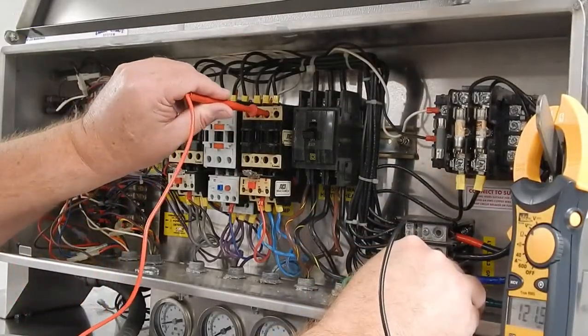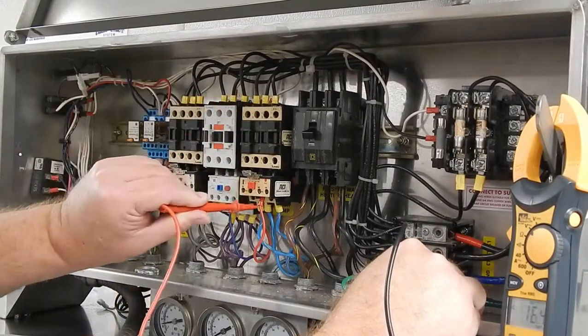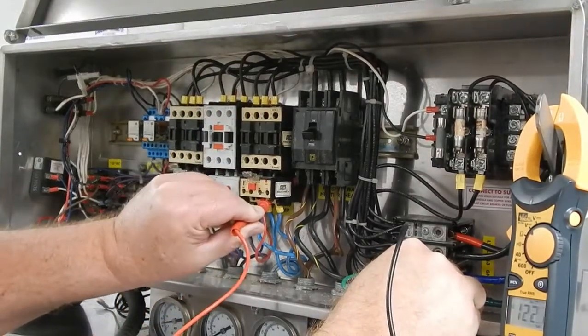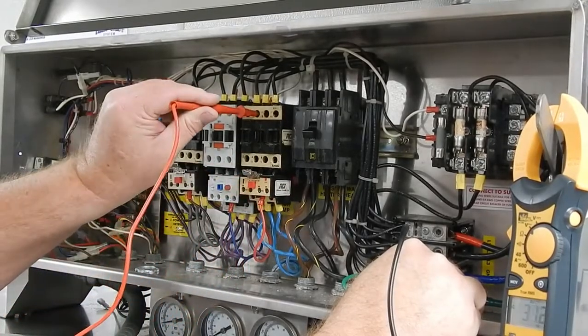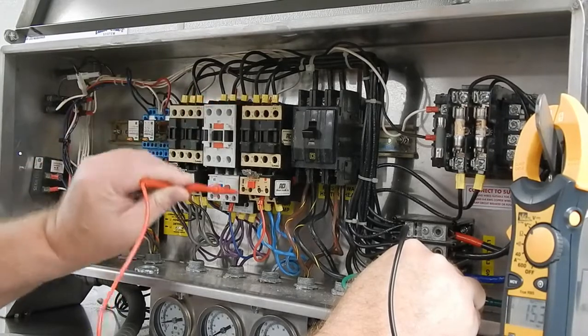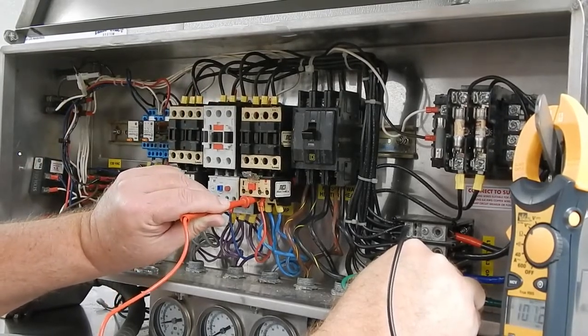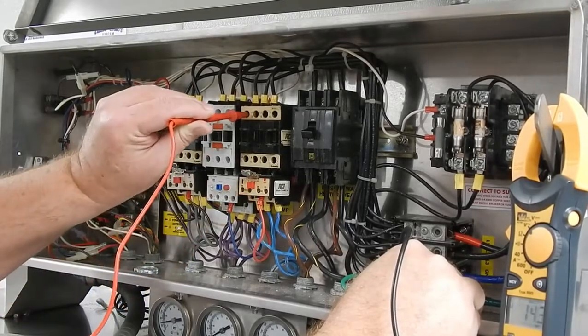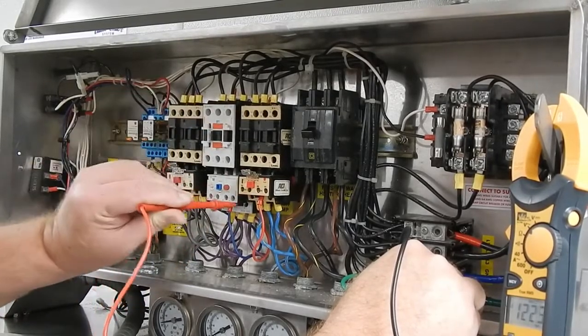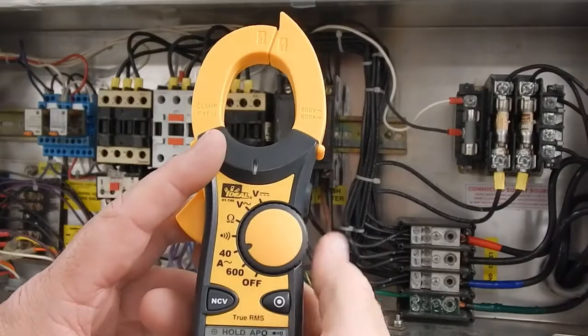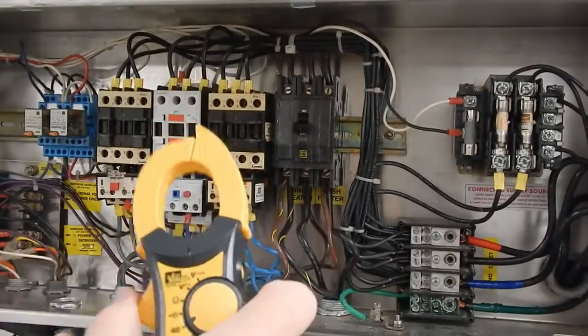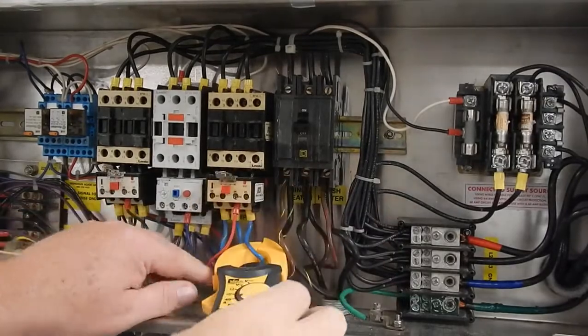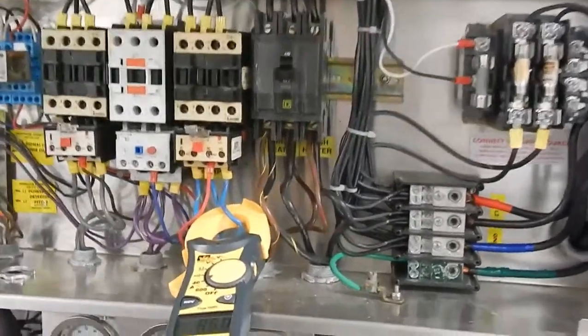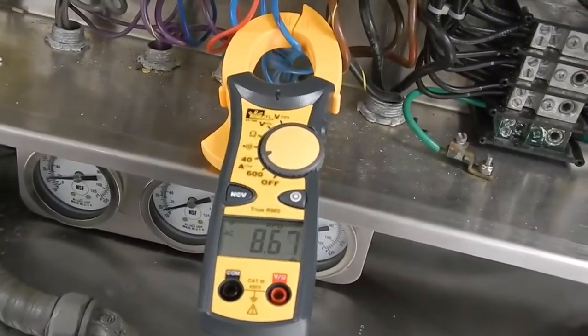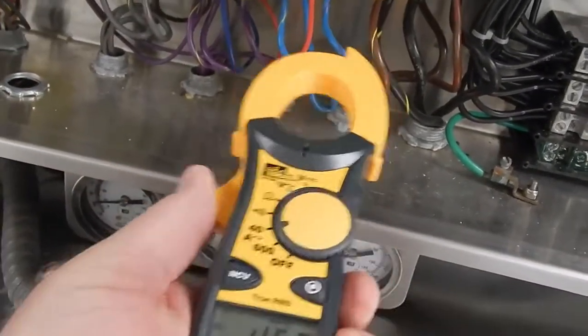Next, we're going to check our voltage coming into the contactor and what's coming out. We want to verify that there is correct voltage on each leg coming through the contactor. Remember, a drop in a leg or low voltage can cause the motor to draw more amperage, causing more current to flow that can trip an overload. Next, we're going to take our multimeter, set it to amp settings, and we're going to test one leg at a time going to the wash motor. We want to check our amps coming through to verify that we're not hitting high amperage. That can also cause it to trip.